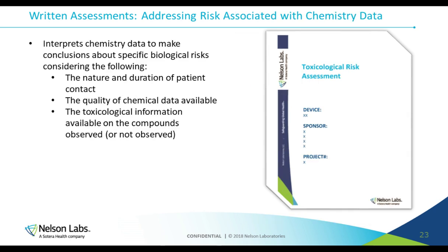Another tool that we use to help understand chemistry data that's used to support the safety of a device is a toxicological risk assessment. What a toxicological risk assessment does is it's not totally independent of new testing. It relies on the results of chemistry testing, and really it's like a translation or an interpretation of a set of chemistry data. So we say, okay, this device underwent chemistry testing, here's what was found. What that means is that the device is safe, or, in case it wasn't safe, that it's not safe.